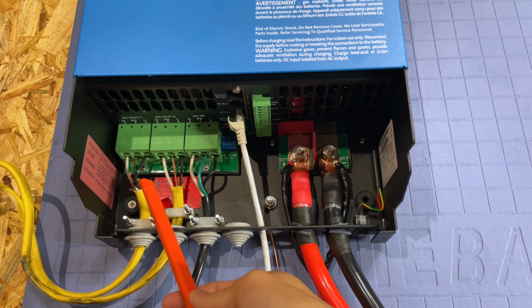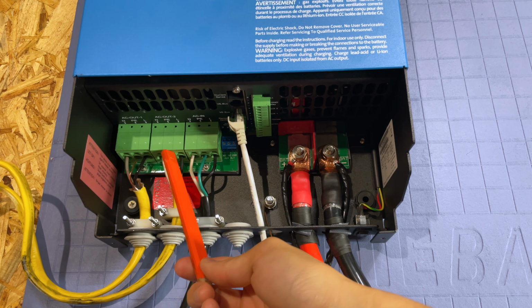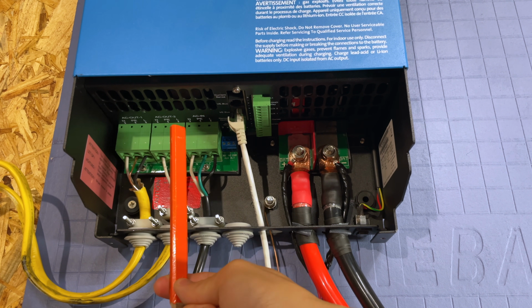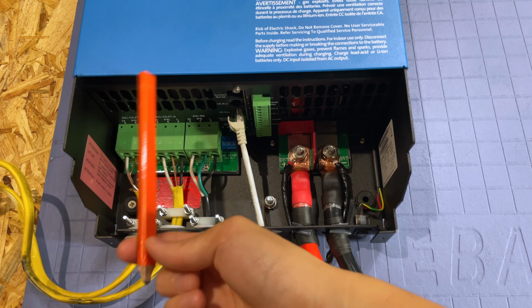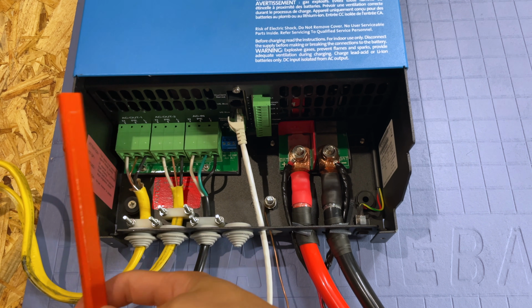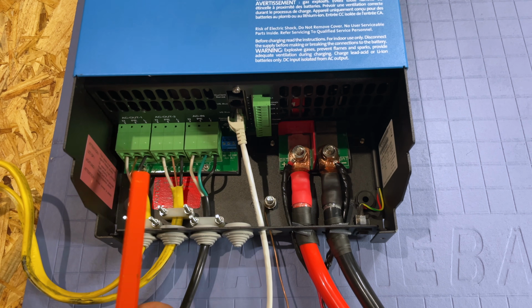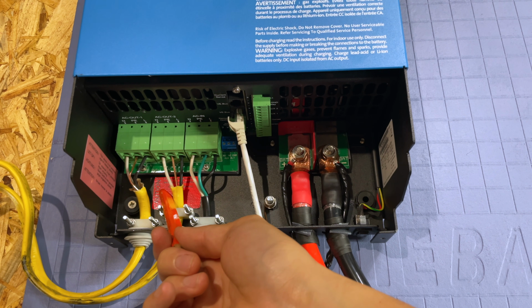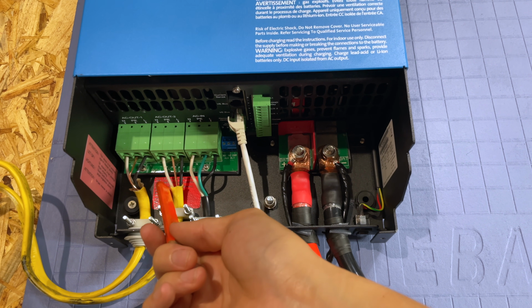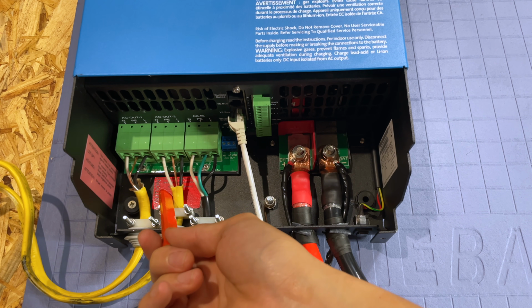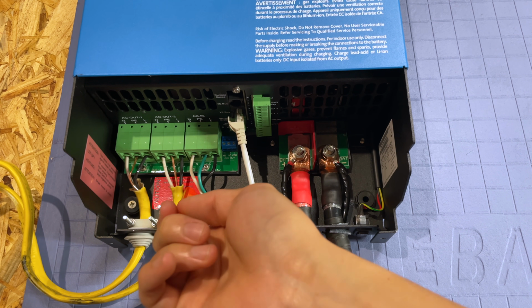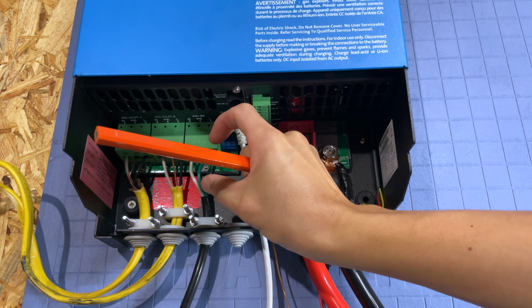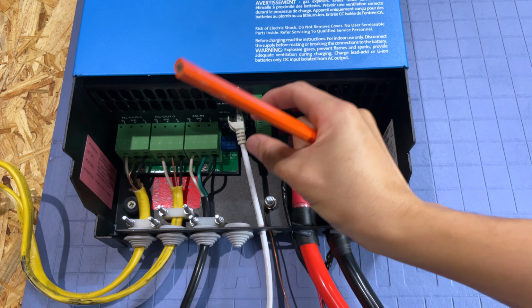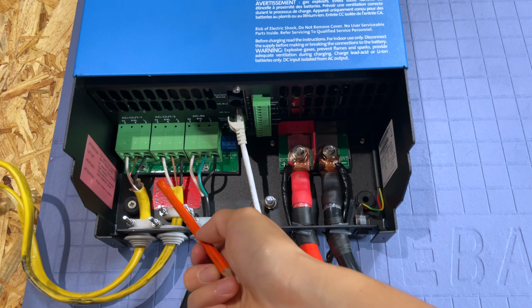If you're using Romex solid core cable, it's not that bad because all you need to do is insert it, and you're probably not going to take it off depending on whatever you're doing. But there are warnings written everywhere, especially here, right? And on the cover and on the label that says you need to insert it a minimum of 0.7. And you need to strip maybe about a whole inch of the wire, but the core of the wire, the conductor, needs to be stripped to about 0.7.